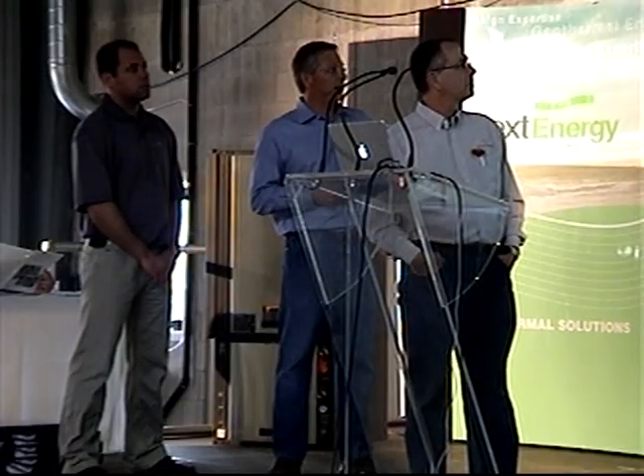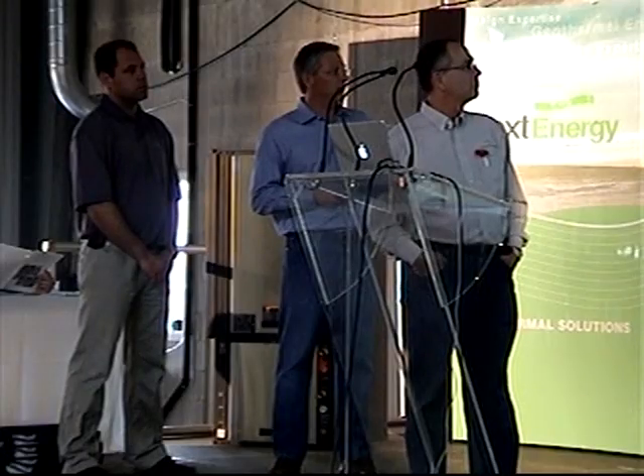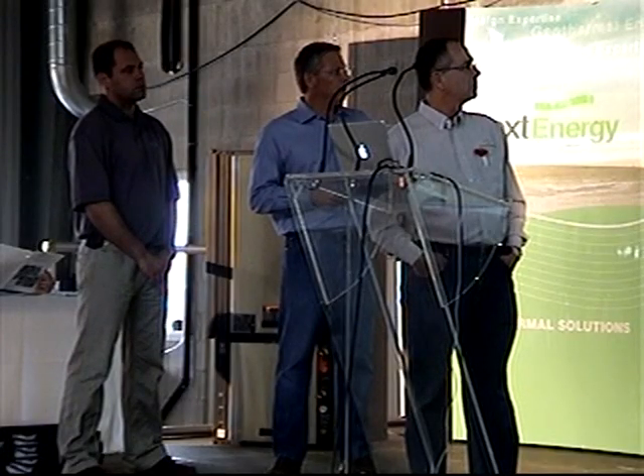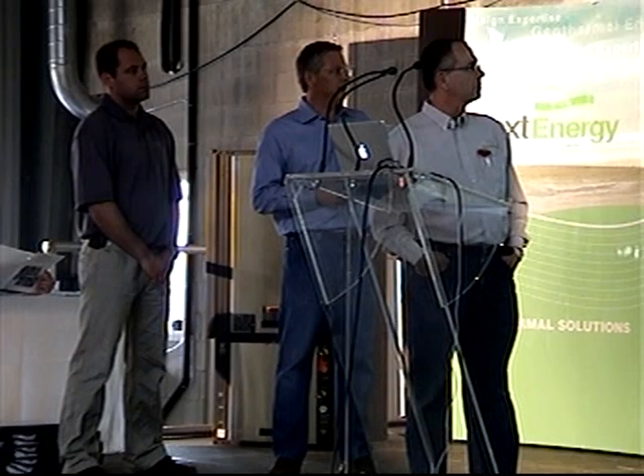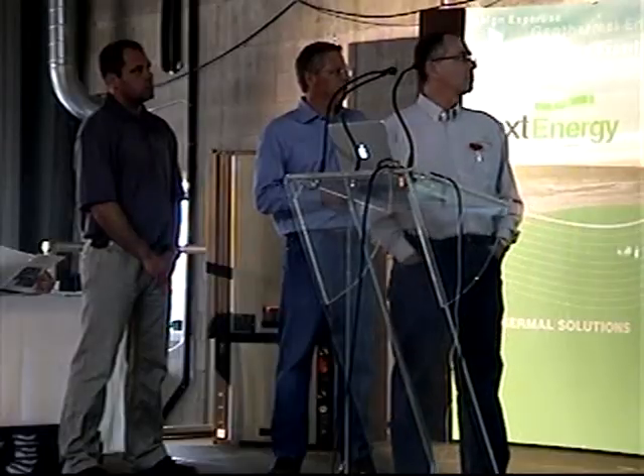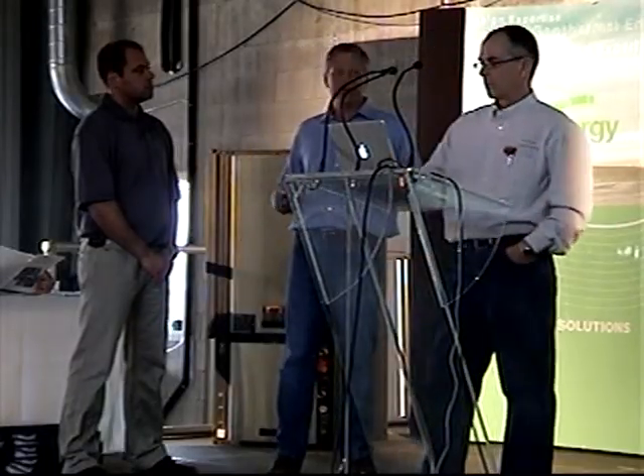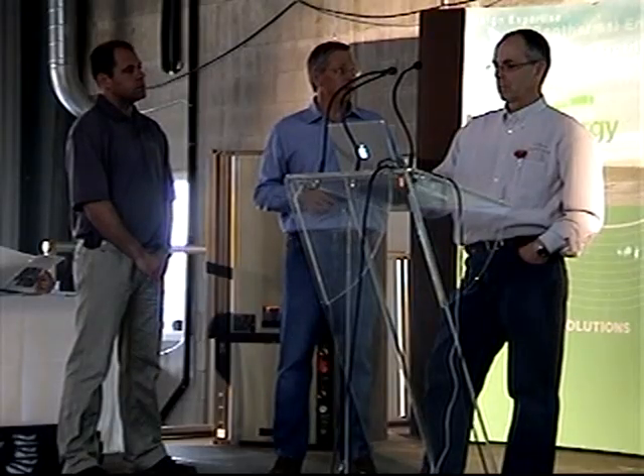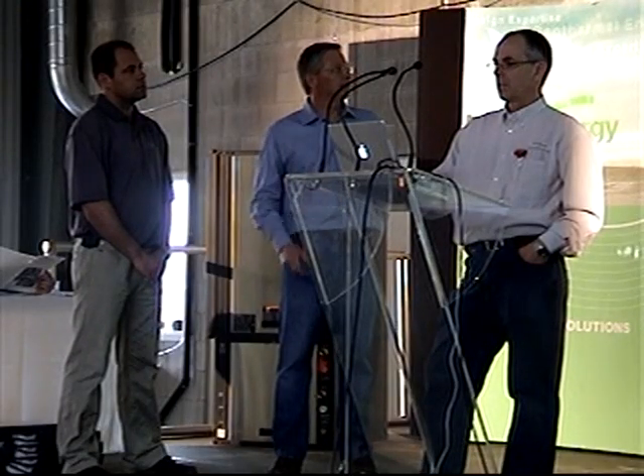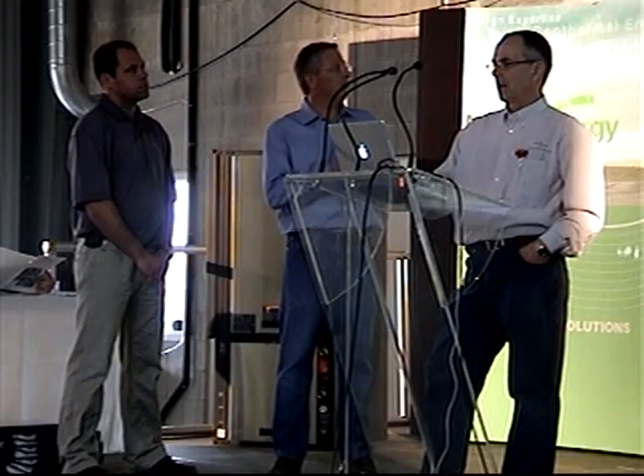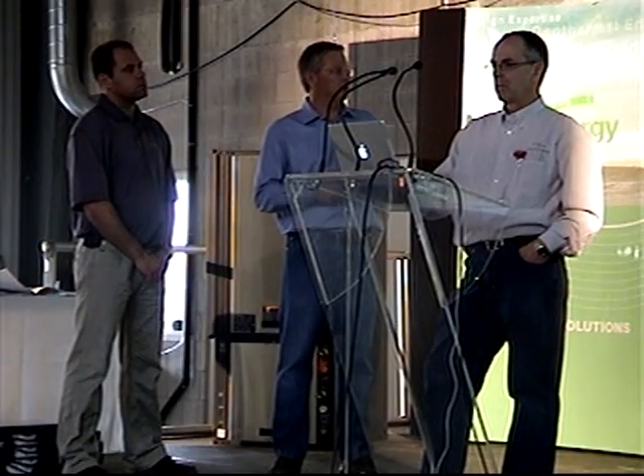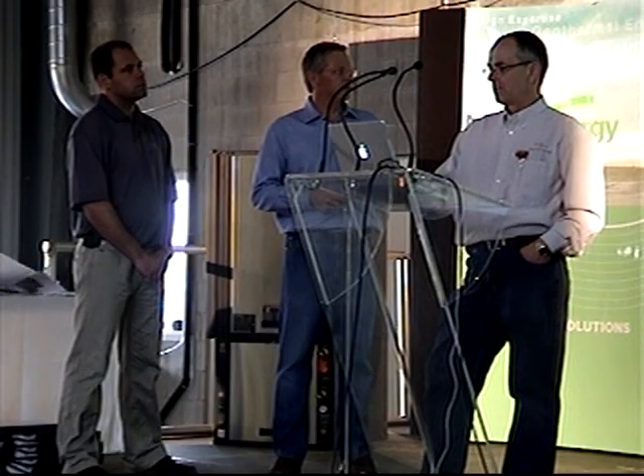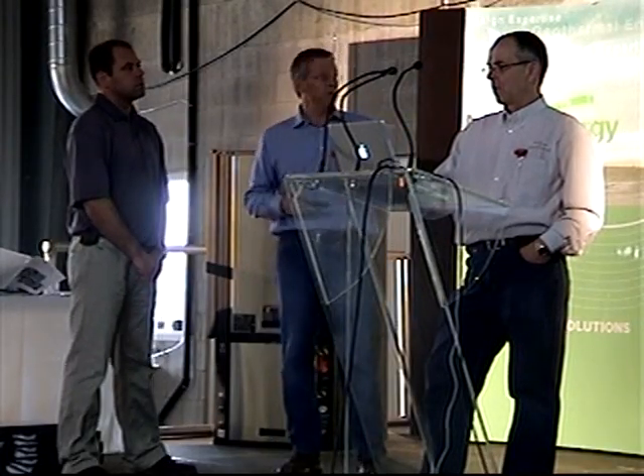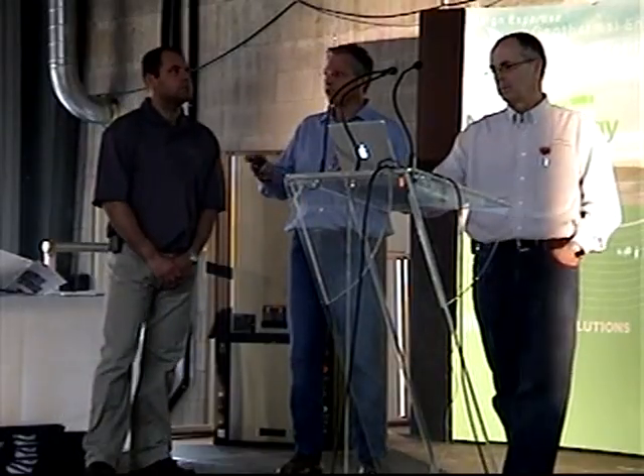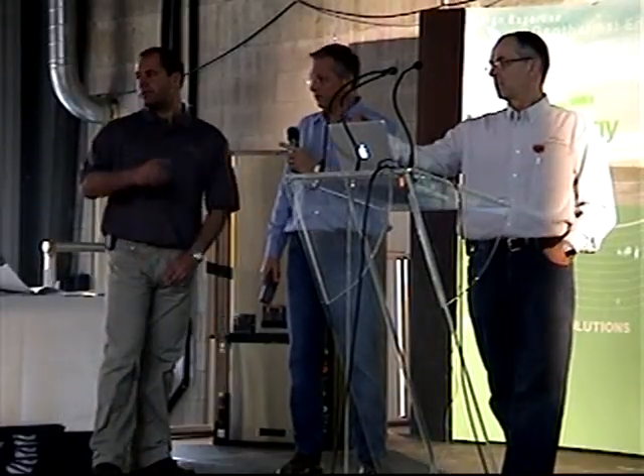Then 5 would be air coil freeze. 6 is condensate overflow. 7 is an over voltage, and it's just a shutdown. As soon as that voltage goes back to normal, it corrects itself. And then 8 says that you had a unit performance sentinel event. Again, that's not a lockout. Then this gets into a whole lot more detail of each one, what causes it. I don't think I need to go through all those, but if anybody's worked with our units and has a question they want to talk about. Freeze protection we're going to talk about later.